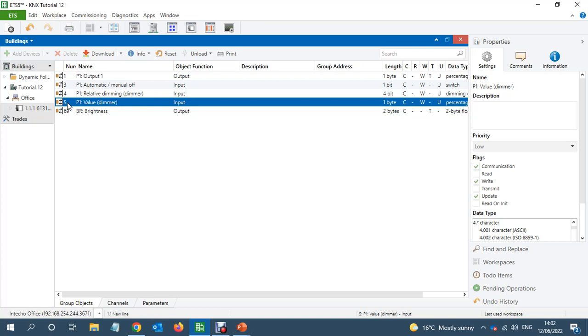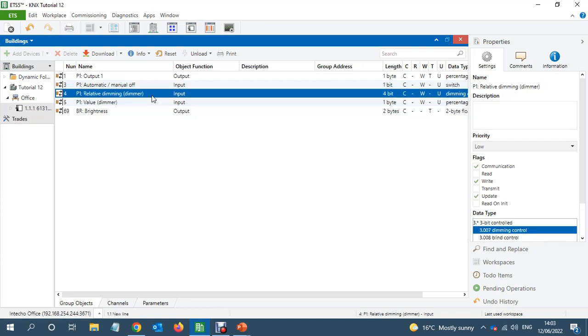After one hour the PIR will kick in again. On the relative dimming, the same way, when they use any object, other device like keypad to increase the dimming, then this will automatically disable the PIR for a while. And then later on, after one hour, the PIR will kick in again.